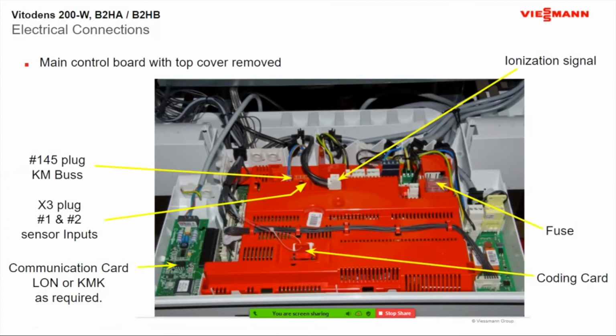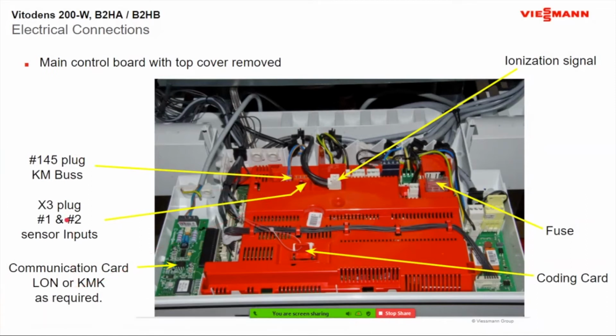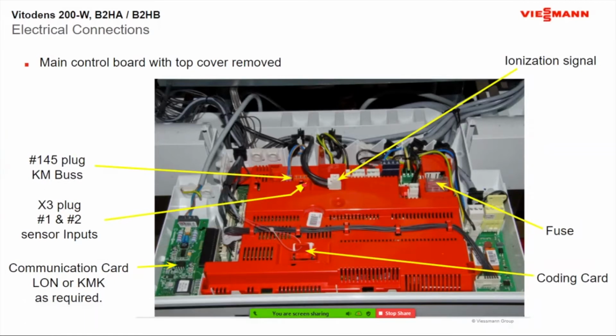Once you do have the cover off, this is what you're looking at here. So now you can see all the different things like a coding card or this orange plug here in the back. You can actually pull it out, then hook your number one, which is your outdoor temperature sensor, in there, as well as your low loss header sensor if you want to do that. And most of the time you're going to do primary, secondary with this boiler. So you can put your number 2 sensor right here on that same plug, called the X3 plug.